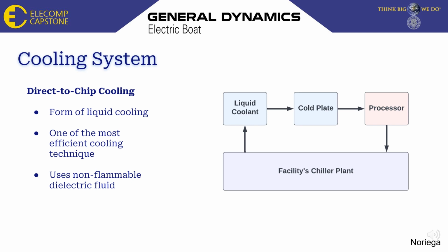One form of cooling is direct-to-chip cooling, a great option as it's one of the most efficient cooling techniques. It uses a non-flammable dielectric fluid that goes to a component's cold plate and cools the processor directly. The liquid is then extracted and sent to the facility's chiller plant to be used again.